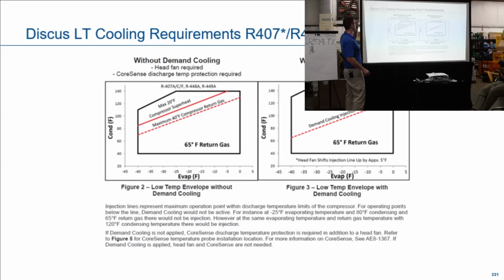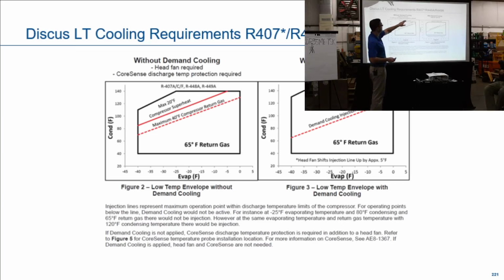Here's another. This is a great point. Demand cooling. What is demand cooling? Does anybody know? Can anyone explain demand cooling to me? Inject liquid refrigerant into the compressor to cool the discharge. Yeah, so it injects refrigerant into the body of the compressor to cool it down. Everybody's okay with that?